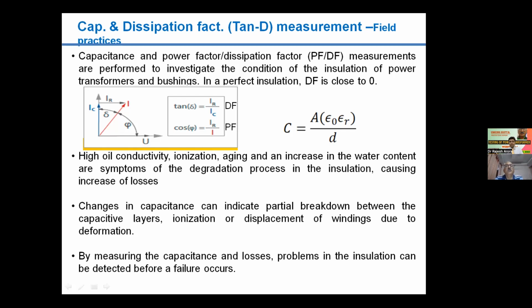Those are also included when you do this test. As you know with any capacitor, the two windings, the insulation between the two windings, and the tank all take part. When you inject a low frequency, low voltage signal to one of the windings, or between two windings, the two windings or the tank and other components inside take the form of an insulator. As I discussed earlier, it is not possible to have a pure insulator. There are always some losses inside the insulator.